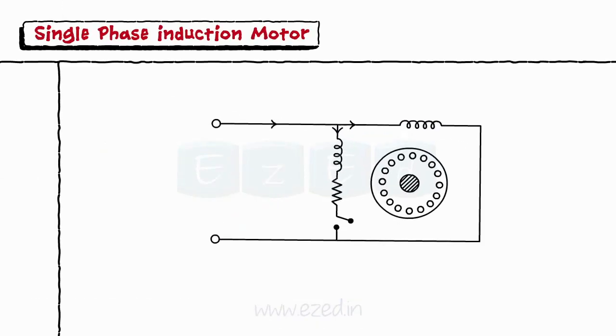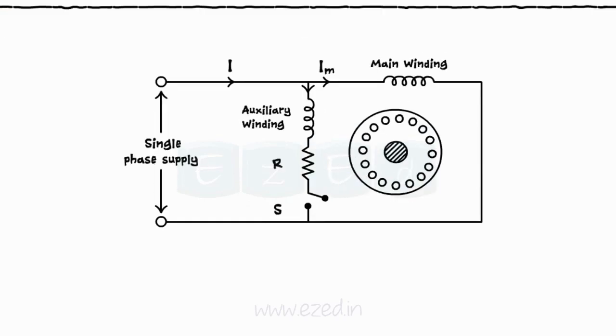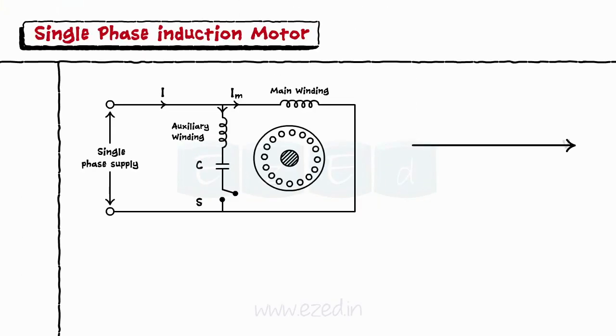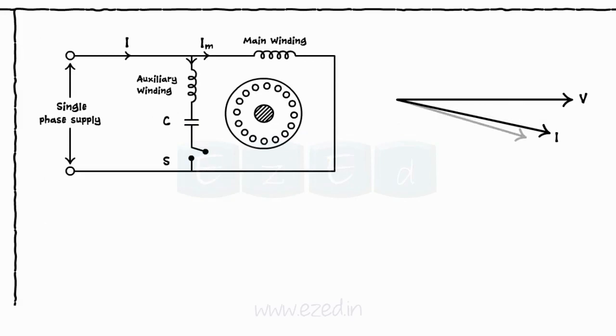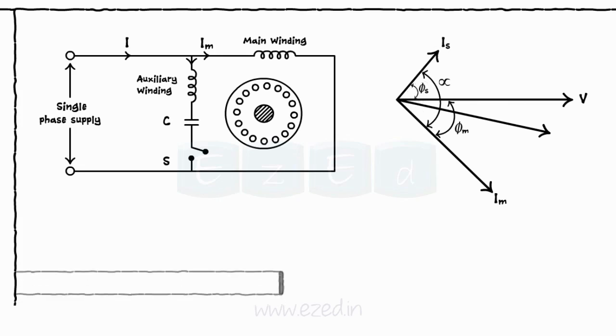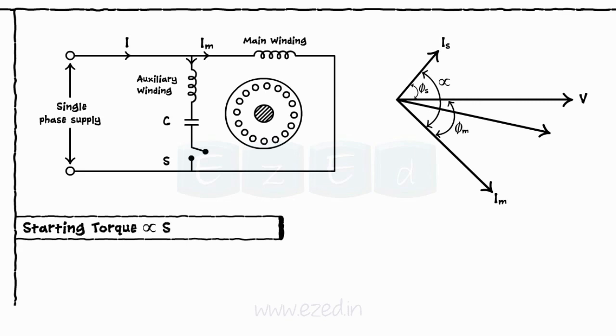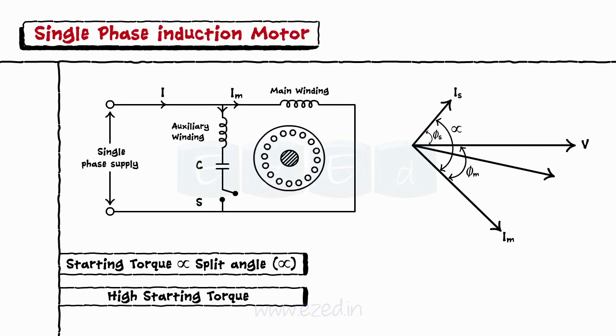The construction of capacitor start motor is very similar to split phase motor. Only difference is the capacitor is used instead of a resistor in series with the auxiliary winding. The capacitor draws the current such that the current leads the voltage. Thus, in the motor, the current IM still lags the voltage but the current IS leads the voltage. This increases the split angle between the two currents. As the starting torque is proportional to this split angle, such motors produce high starting torque and motor starts its rotation.